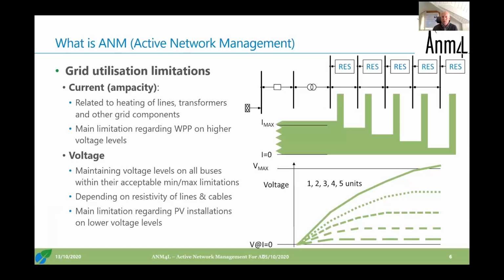On a generalized level, we can say wind power plants' main limitation is related to ampacity in the grid. On the other hand, we have voltage, which is more of a top-down limitation, where voltage levels on the higher level in the grid affect things downward. When we have production units in the low voltage grids, the voltage profiles we see in the distribution grids go in the opposite way than they normally would in a grid that is normally loaded.